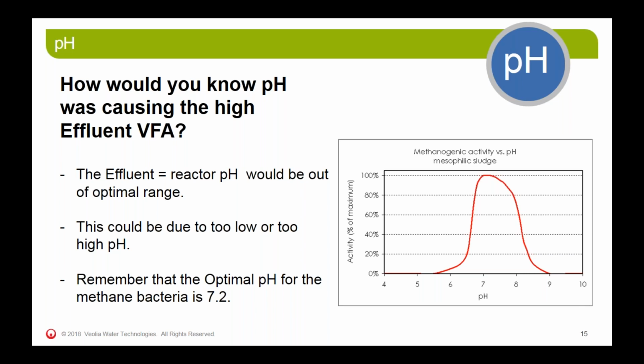Now, I know that not everybody operates their reactor effluent pH at 7.2 because that costs a lot of money for caustic most of the time. So a lot of people, I know a lot of systems run lower than that, 6.8, 6.5 even. And if you're running below that optimal level, you have to be really careful that your control system is really spot on because you're running on the edge. Okay?